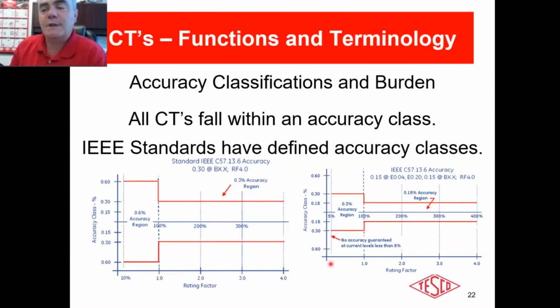and then it works down to 5%. Well, since I put this slide together several years ago, the transformer manufacturers have improved on this, and I really need to update my slide. Many of the best transformers you can buy now are 0.15 all the way down, and this 5% is now arguably down to 1% or better. Some manufacturers claim they can go all the way down. We've never seen that in the lab. I'm not saying that they can't do it, but they're better than 1%.